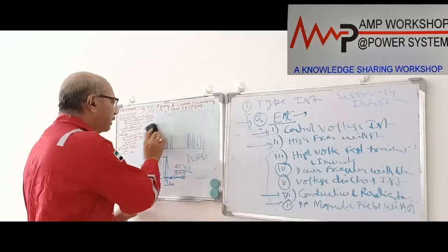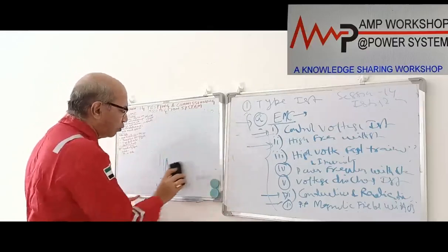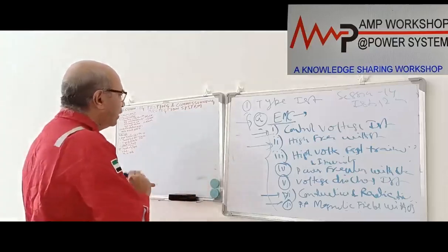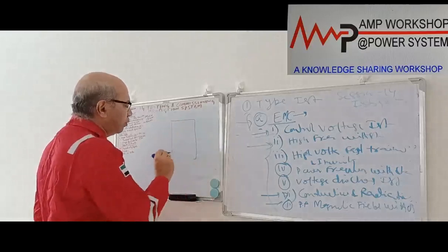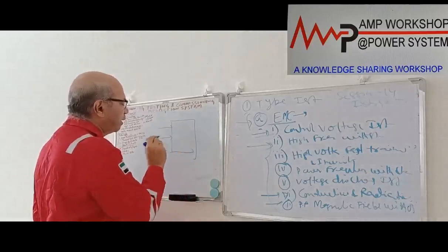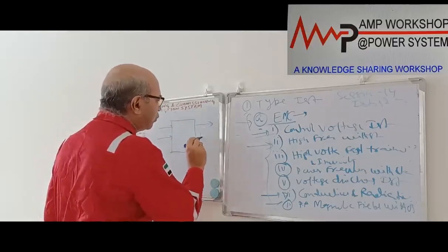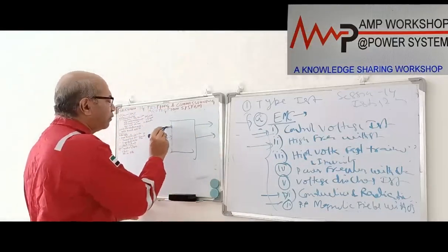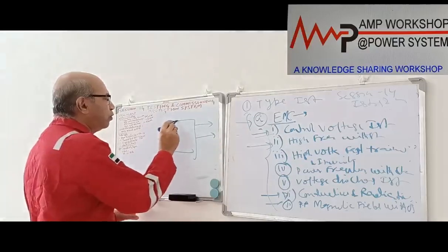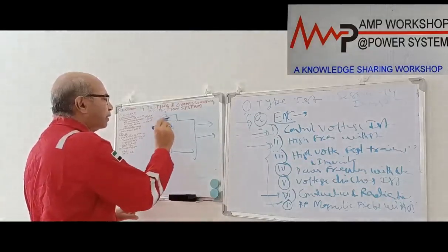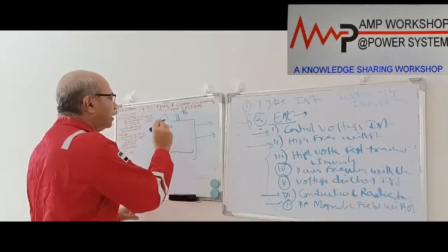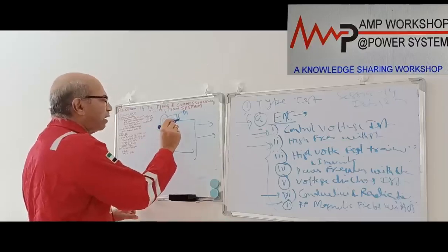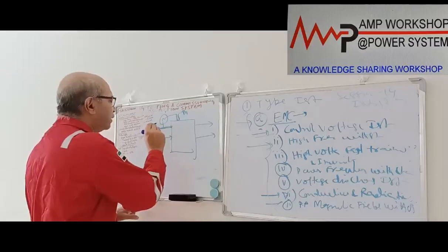We have to discuss another point. There are two points we discussed: one is common mode injection and the other is differential mode injection. What is that? In the relay we have seen there are various inputs. Suppose this is a CT input, this is a PT input, and suppose this is a relay output, various outputs. Now when we test one of the inputs with respect to the casing, the casing is grounded and the voltage is applied between the input and ground, that means an independent circuit to the ground. Then we call it common mode testing.